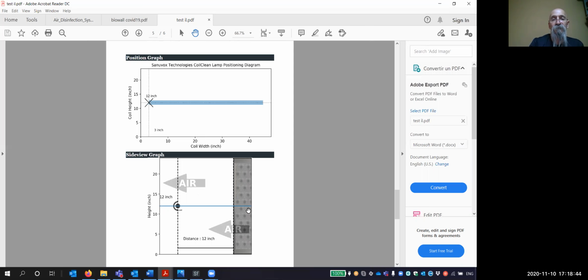So air moving through the coil at the lamp would be considered downstream, whereas if the air is coming this way and the lamp's located here at the coil, that would be upstream. When you have a downstream application, you have the air going against the lamp. This will promote fouling, so we do have our calculation accommodate for that. Fouling is collection of dust. Anybody that wears glasses, if we walk very slow, our glasses get dusty.